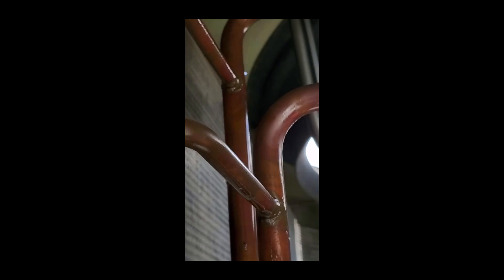So anyway, I ended up leak searching this whole area and I finally found it back there. Even with it spewing out, with all this other equipment around me I really can't hear - I was trying to stick my head in there and I still really can't hear, and I'm right here by it. So what I'll probably do - they gave me a zip tie, two zip ties - and strap them down on here on these two. That's where it's leaking. So I know when I come back. I think I'm gonna go to lunch real quick, take a break.